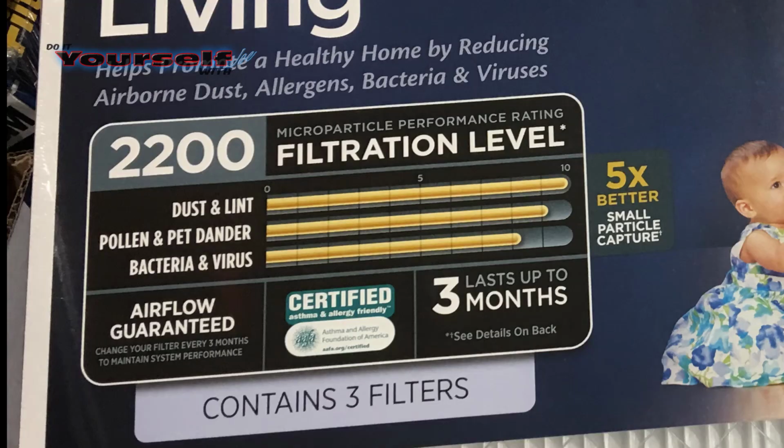One drawback to these filters is the amount of airflow they let through. Also, as they collect dust, they choke the air even more. This has a rippling effect. The less airflow, the longer it takes to heat or cool your home. This is a lot less important with newer furnaces. When you have an older furnace that may be struggling to heat your home, buying and installing a filter that collects more dust may not be a great idea. It will also cost you more money in the long run to heat or cool your home because the furnace will run longer.